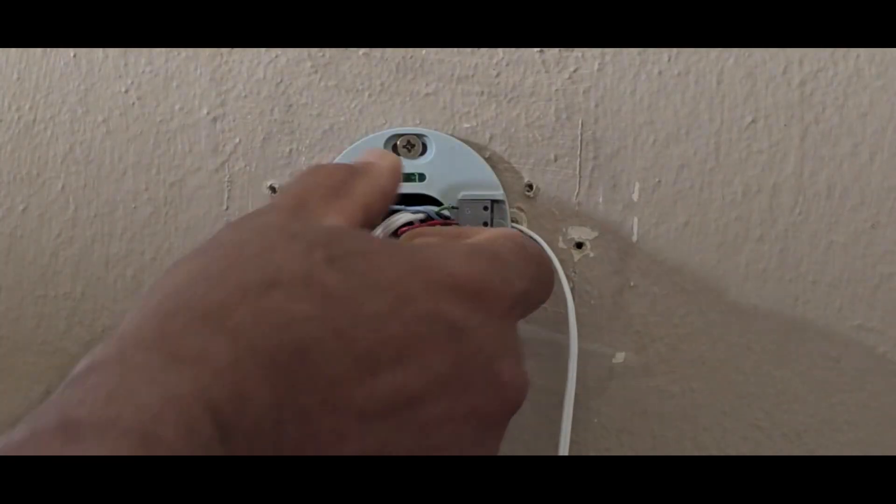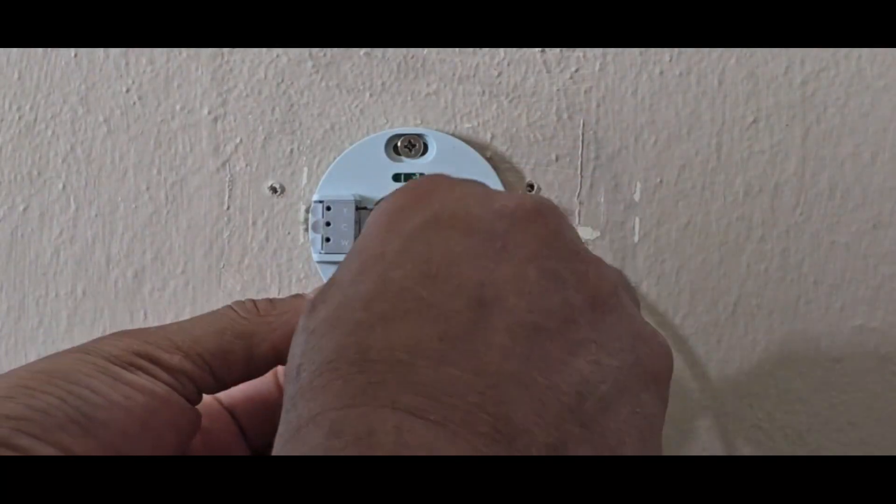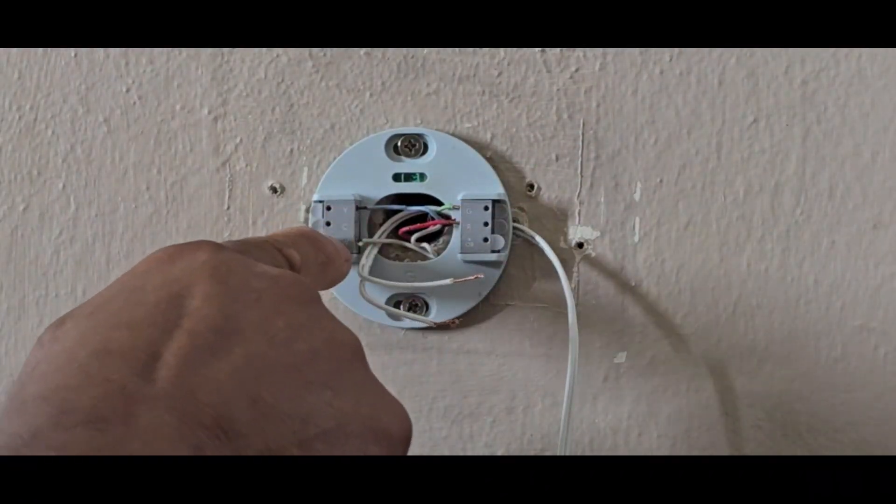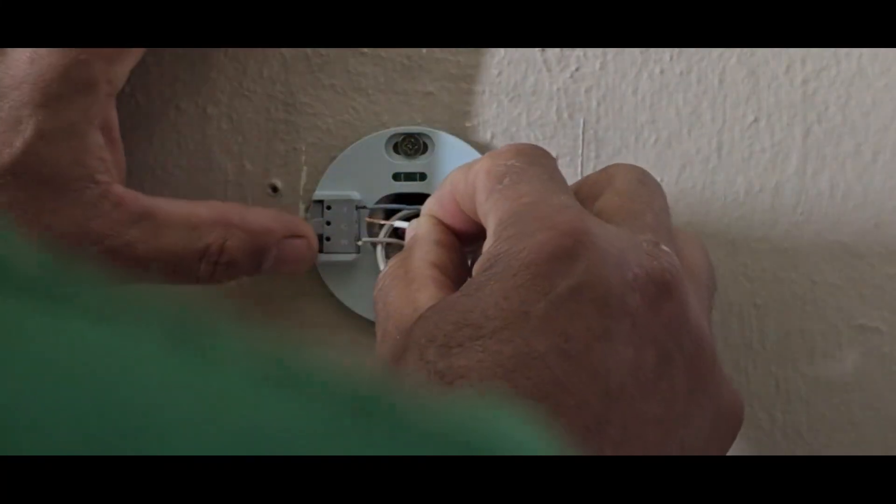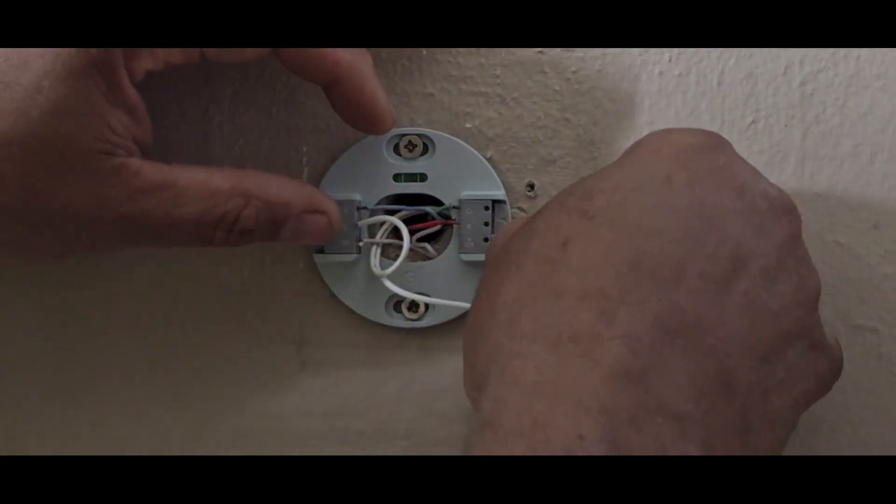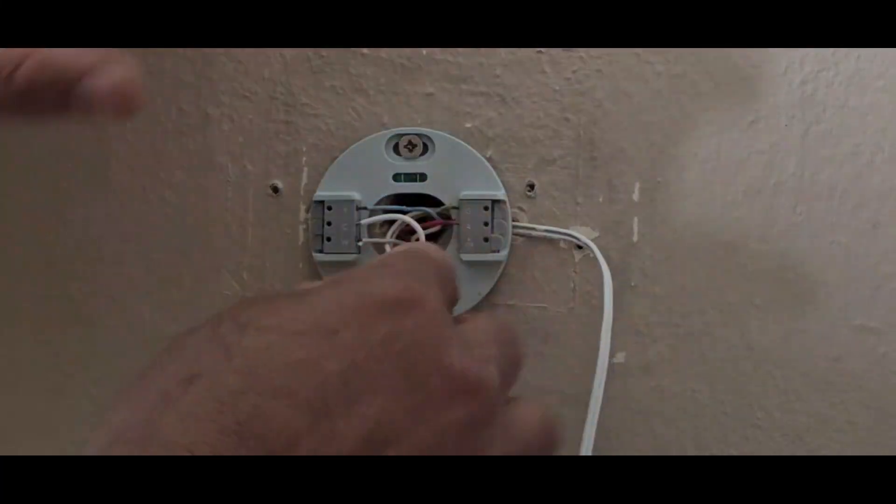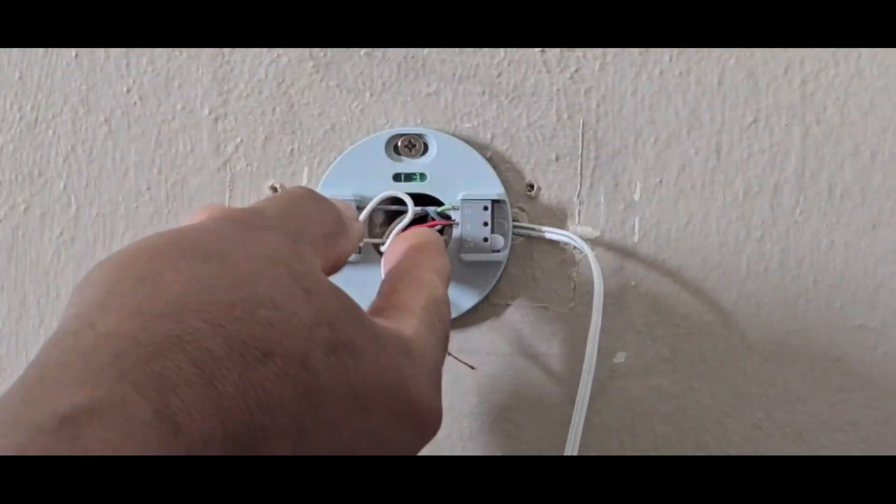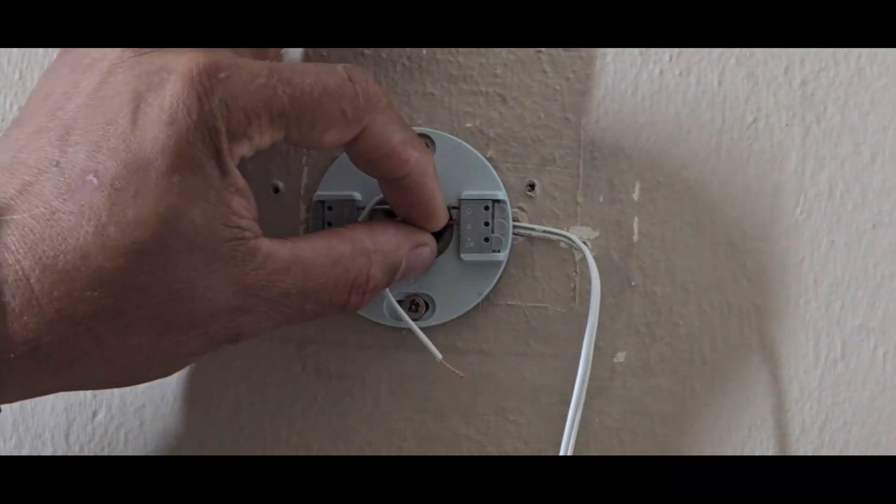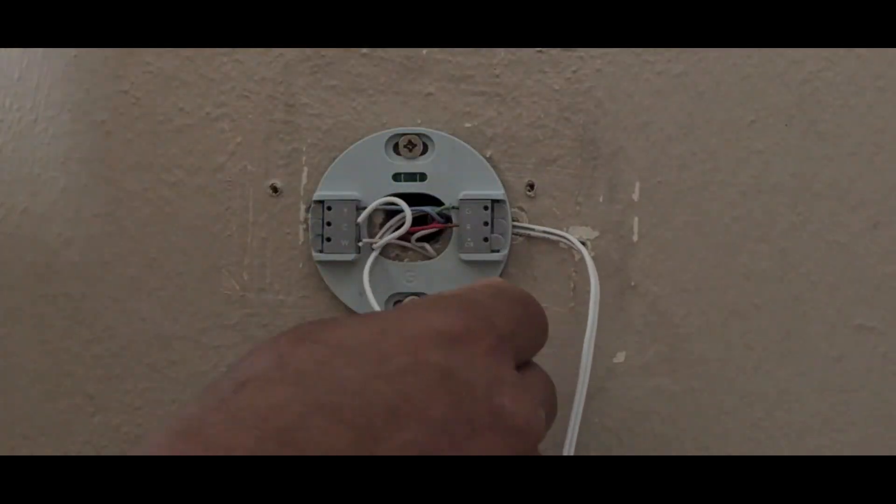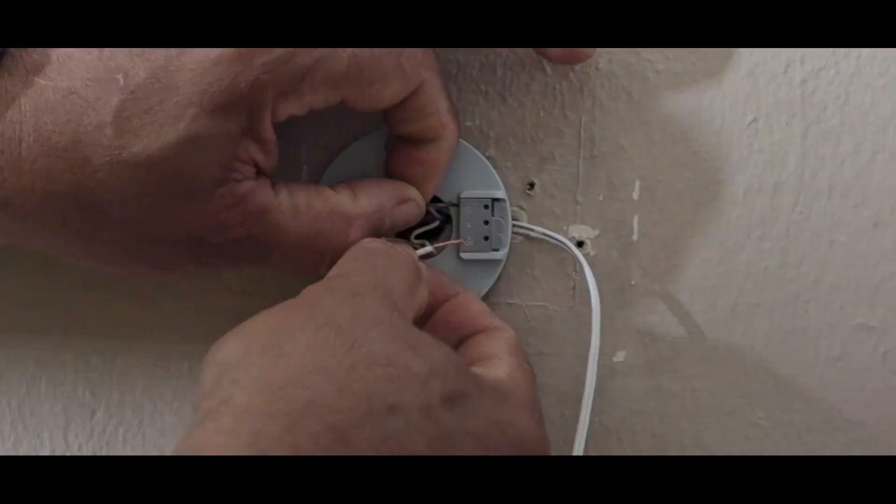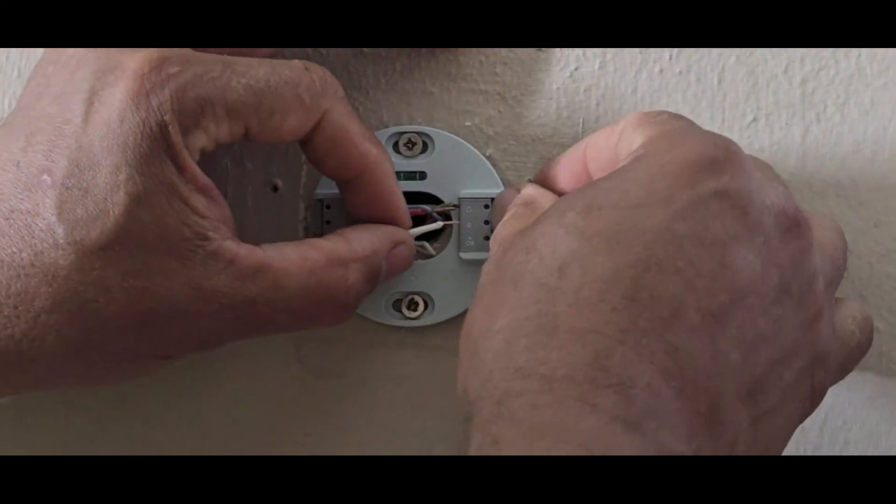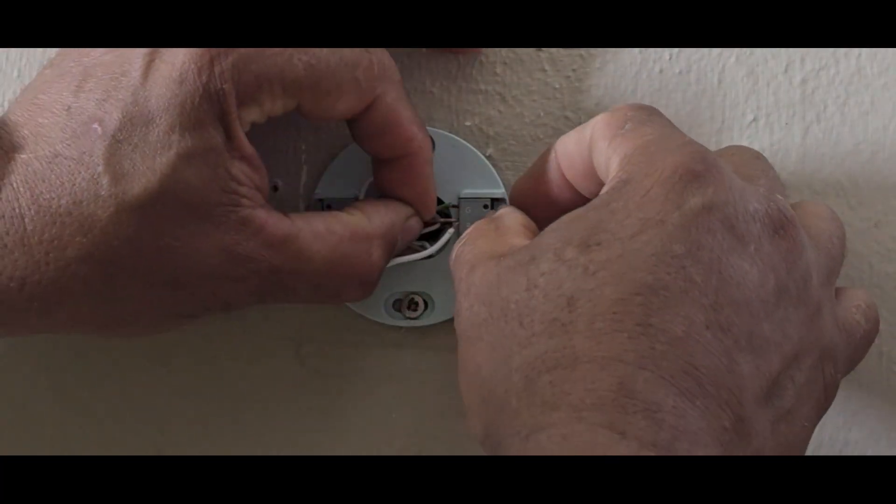I'm going to have this cable come through here. This one is a bit different from the one downstairs. We're going to put the wire in the C and the R terminals - you can see there's nothing there. Push that in until it clicks. This one here, we're going to use the R terminal and share it. Press this down and take this out. I'm going to put this one in first, and then force this one in.